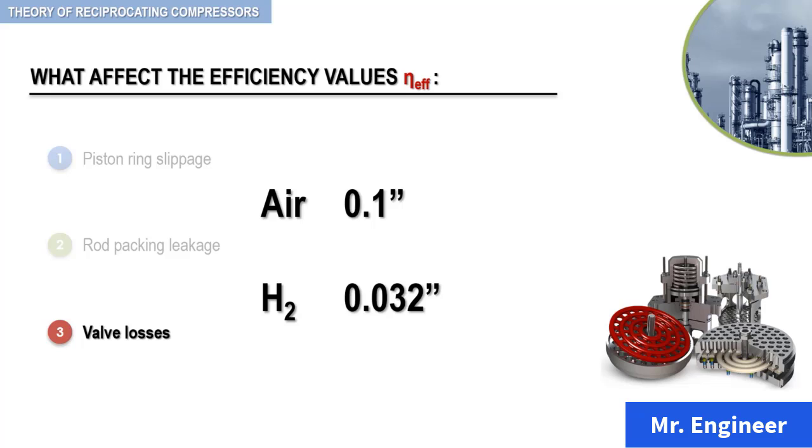The valve porting influences volumetric efficiency by contributing to the minimum clearance volume. If the porting must be enlarged to reduce the flow loss, it is done at the expense of minimum clearance volume. This is just one example of the many compromises the design engineer faces while designing the reciprocating compressor.